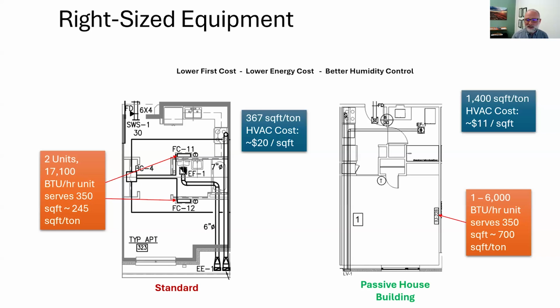So this slide shows a comparison of two similar multifamily projects with studio apartments. The project on the left used 2 wall-mounted indoor units to serve the apartment, one in the kitchen area and one in the living room. And this resulted in an increased outdoor unit capacity and a huge increase in equipment costs. The project on the right used one 6,000 BTU per hour wall-mounted unit for the apartment, which was still oversized compared to realistic loads, but was the minimum equipment size available at the time.